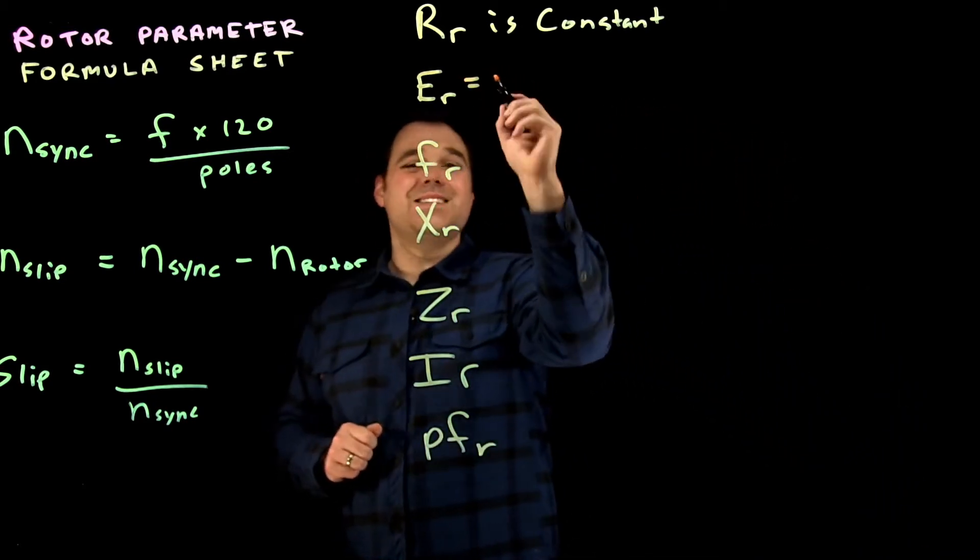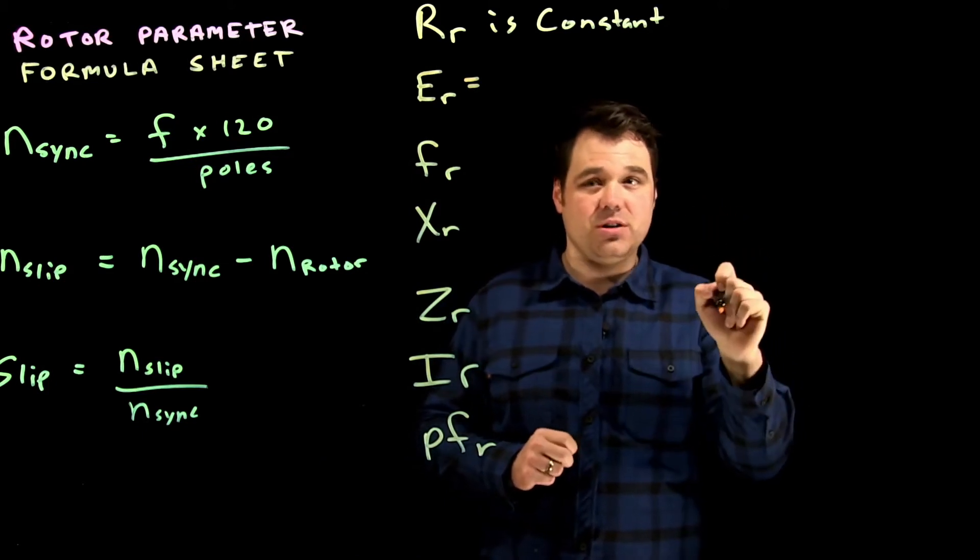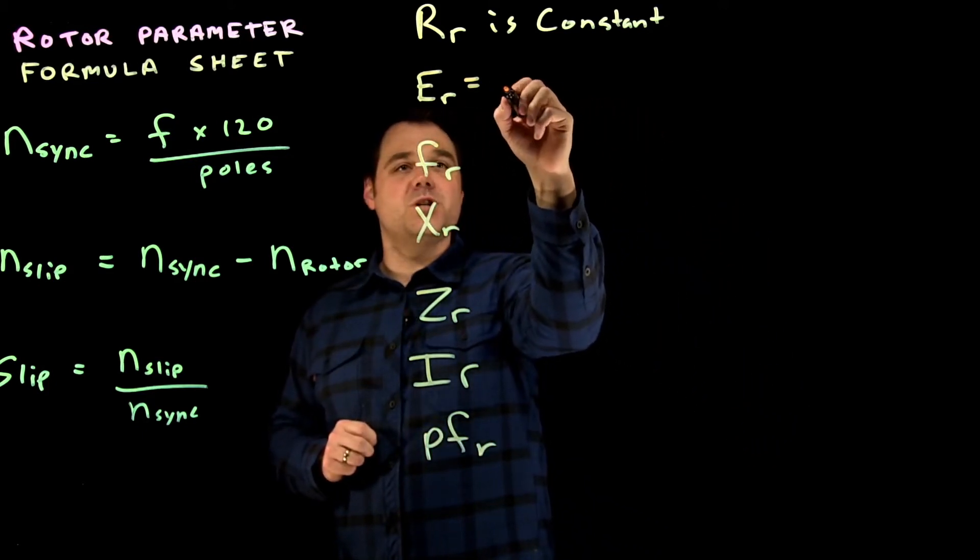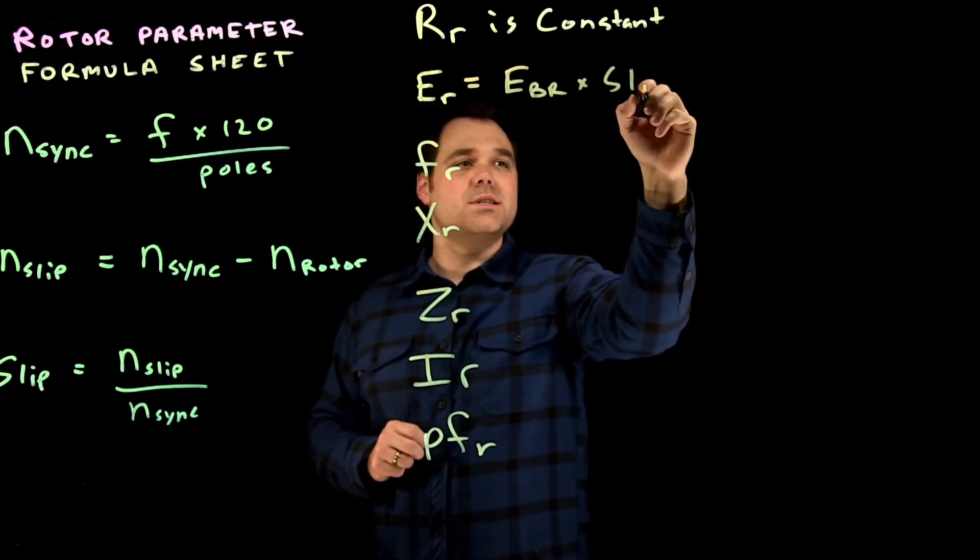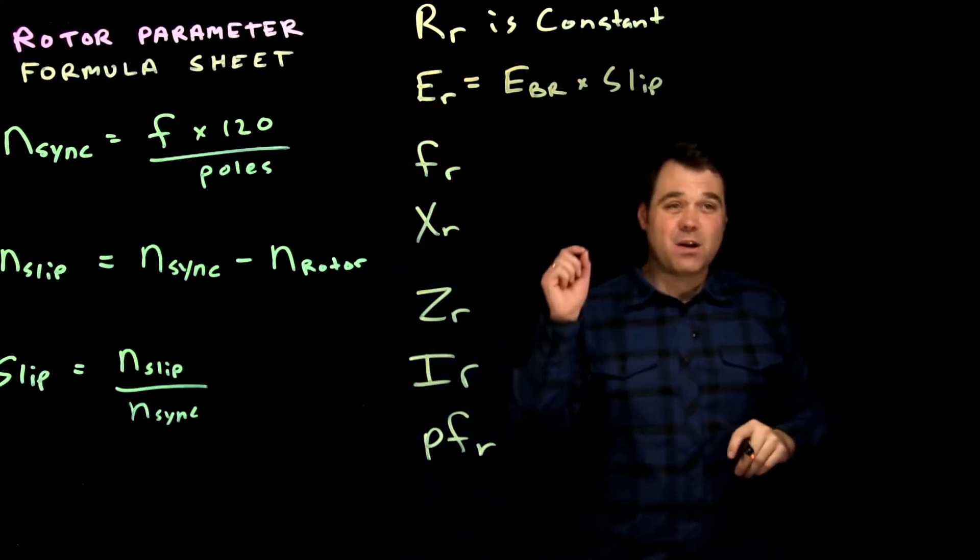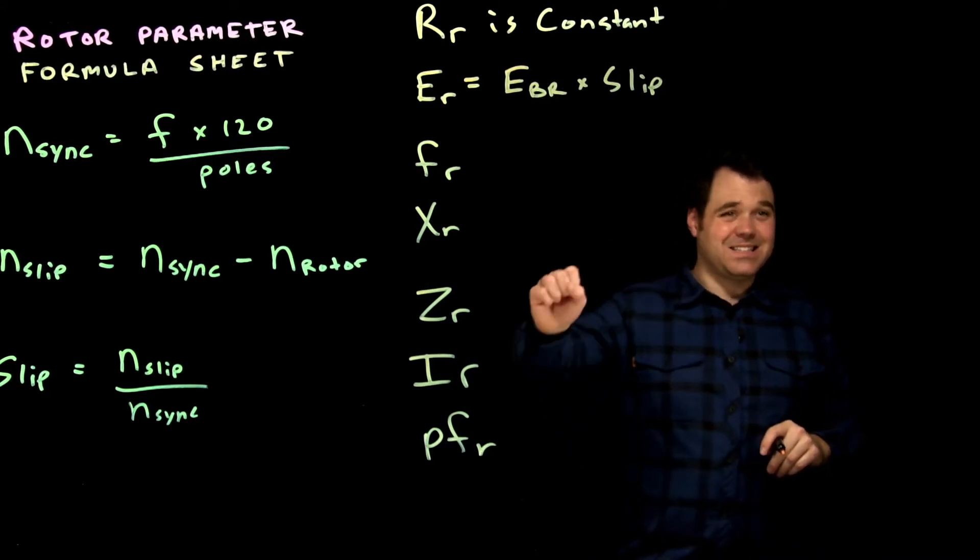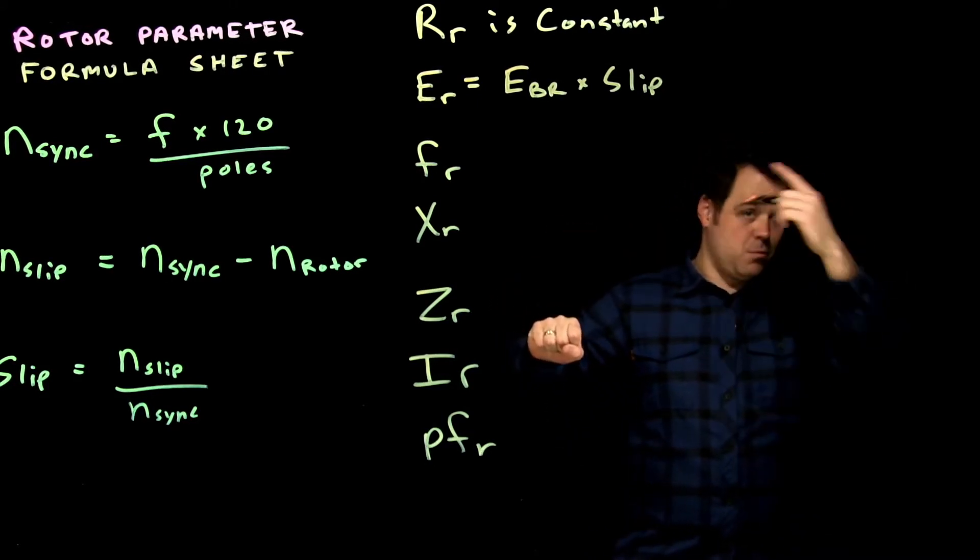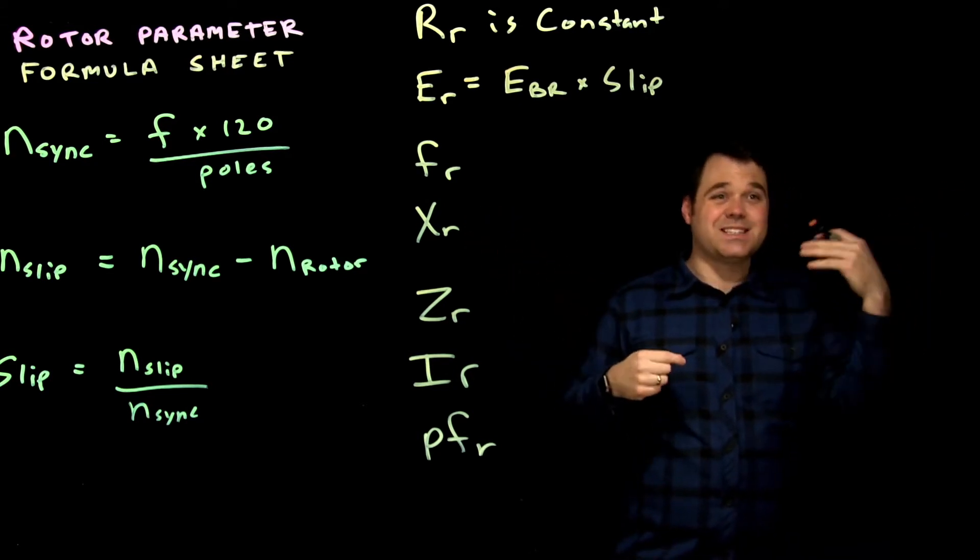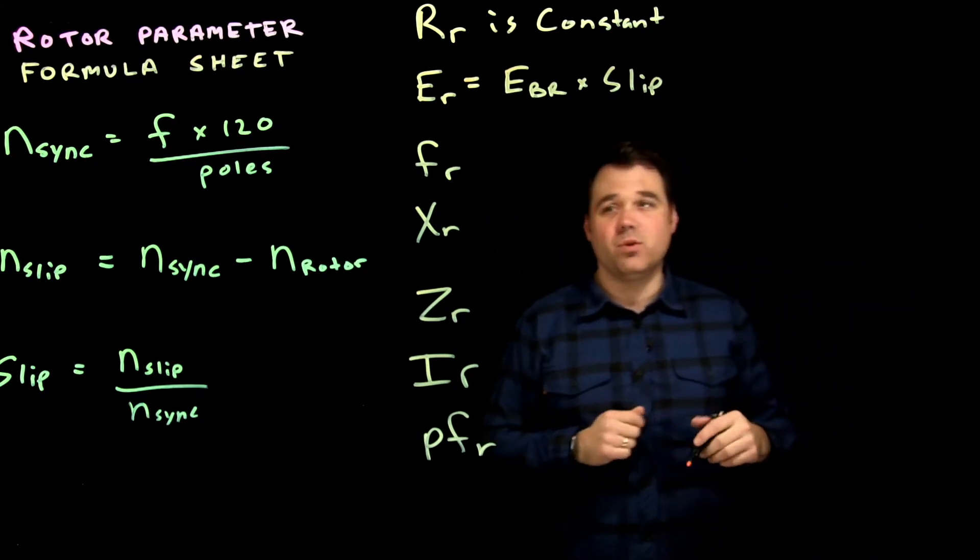Voltage is directly proportional, which means that it will just be the voltage of the blocked rotor times slip. Now blocked rotor is when that rotor is not spinning, it's zero RPM, it's at a standstill and my stator is spinning at 100% or my synchronous speed. So that's a slip of 100% is my blocked rotor voltage.